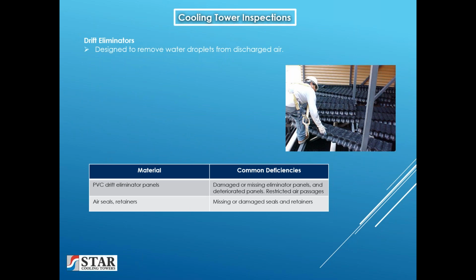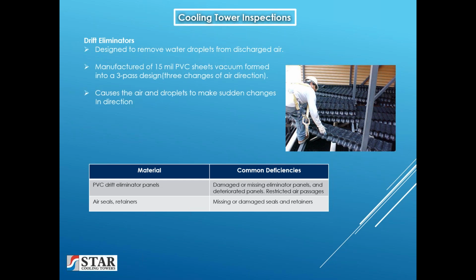Drift Eliminators are designed to remove water droplets from the discharged air. Manufactured of 15 mil PVC sheets, vacuum formed into a 3-pass design. The 3-pass means there's 3 changes of air direction. It causes the air droplets to make sudden changes in direction. The droplets are deposited back into the tower.